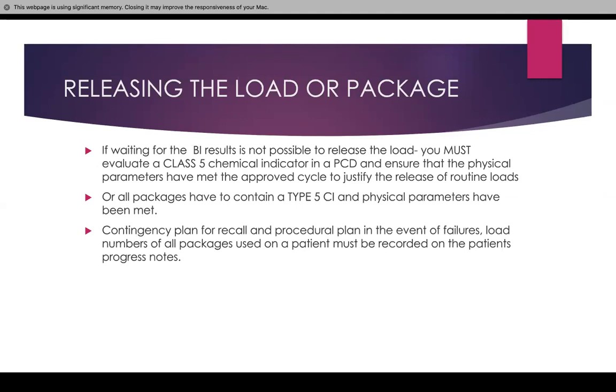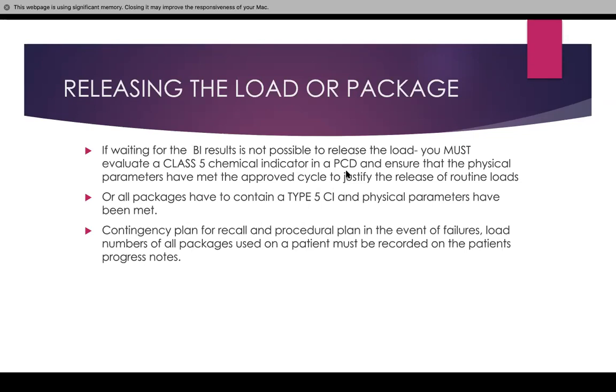All packages have to have a type 5, class 5 indicator if we're not placing it in the PCD. The easier choice is to not place the class 5 indicator in every pouch, but with every cycle, place a PCD with a class 5 chemical indicator.